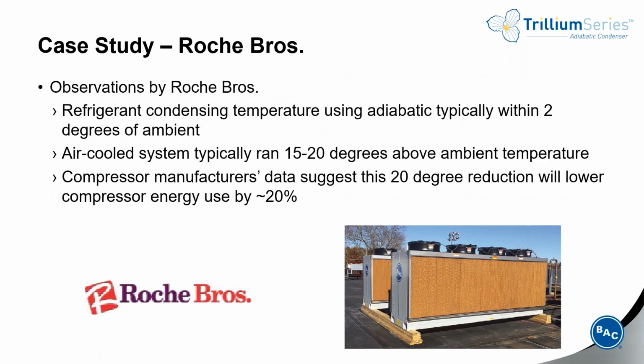After completion of the project, some observations by Roche Bros. were that they noticed their adiabatic condensers were able to achieve condensing temperatures within about 2 or 3 degrees of ambient temperatures. Contrast that with their air-cooled systems, where they were noticing condensing temperatures about 15 to 20 degrees above ambient temperatures. Compressor manufacturers' data suggests that this 20-degree reduction in condensing temperature will yield about 20% reduction in compressor usage. So this turned out to be a really nice project for them.